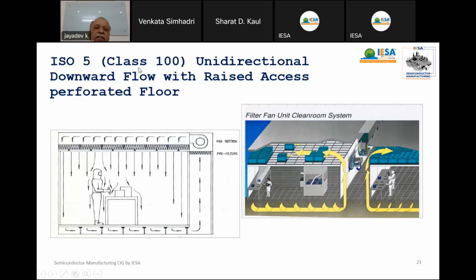So this is a class 100 unidirectional flow. This is a picture. See, vertical air flows down to the graded flooring and recirculates. We call it vertical laminar flow or unidirectional flow air. It goes directly parallel to the flow. So this can be achieved by using fan filter units.